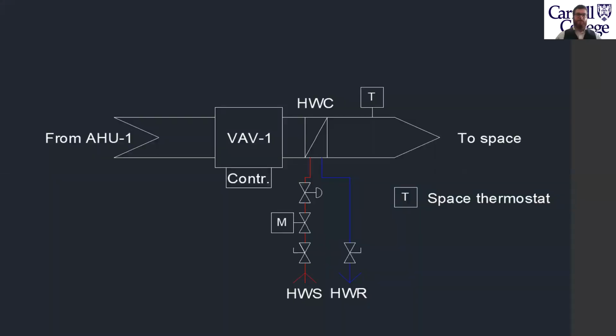To explain a VAV system, I've included a detail of a VAV terminal unit. The terminal unit is what controls the temperature of the air and the amount of air going to a zone. Air comes from the air handling unit at 55 degrees, and then the volume of air is changed by a damper inside the VAV box. The air can then be heated by a hot water coil, so the air can be changed from 55 degrees all the way up to 90 degrees if max heating is needed.